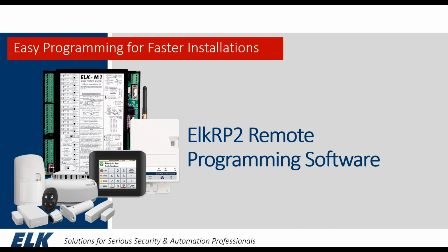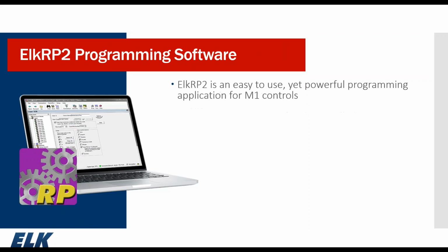There's also firmware updates. If there's a particular manufacturer that we're now working with, you can update the M1 or the XSP and so forth to work with that new partner manufacturer. But I think you'll find that the RP2 software is really easy to navigate. It's a very powerful programming software language, but still very easy to use. It includes what we call conflict resolution. So as soon as you connect to the panel, it's going to check the differences between what's in your database or on your computer versus what's actually programmed in the panel, and it'll return those as conflicts. And you can resolve those by either receiving from the panel or sending data to the panel. So you have the option there to resolve those conflicts.